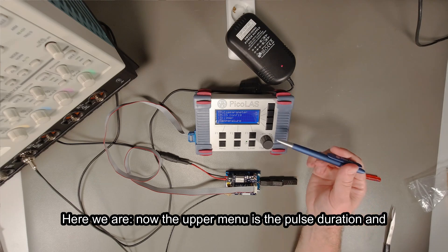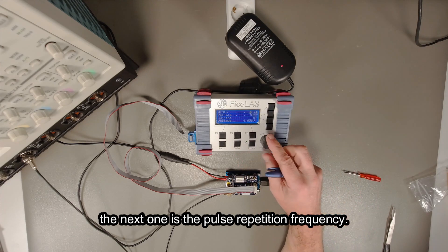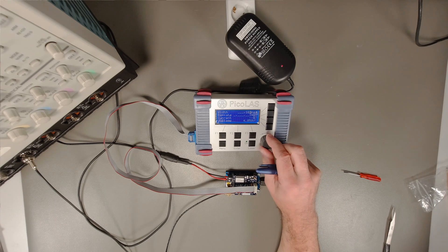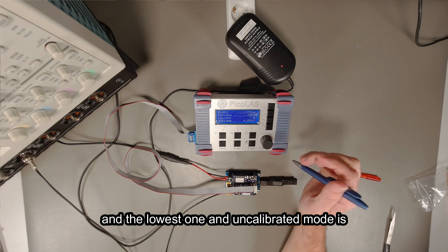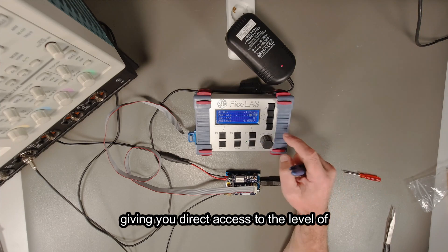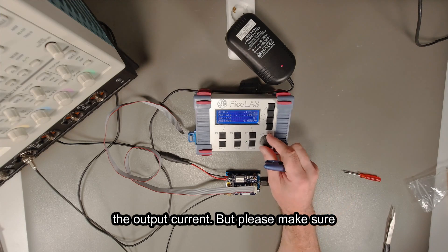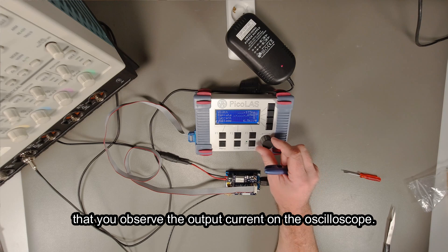The upper menu is the pulse duration. The next one is the pulse repetition frequency. The lowest one in the uncalibrated mode gives you direct access to the level of the output current. But please make sure that you observe the output current on the oscilloscope.